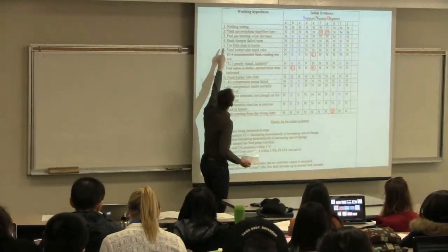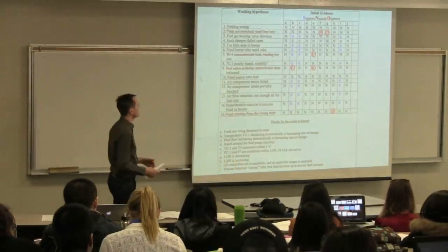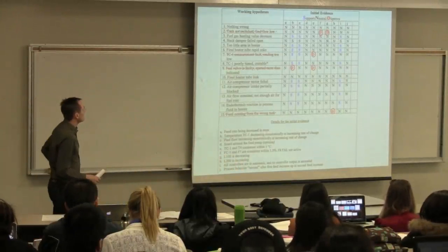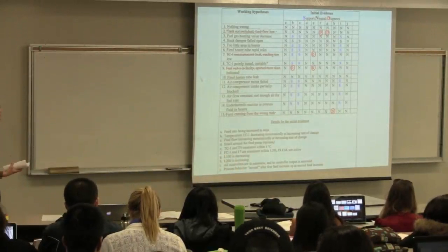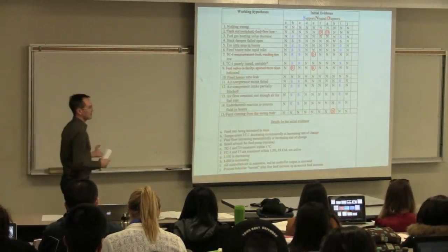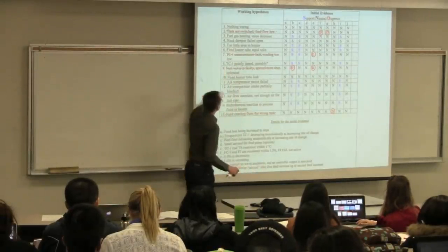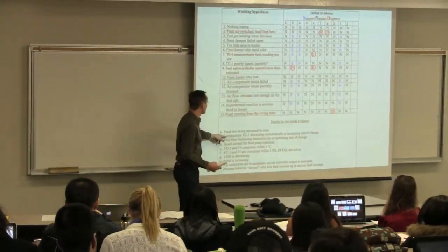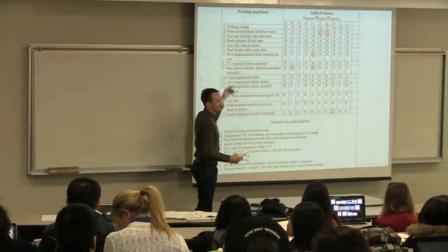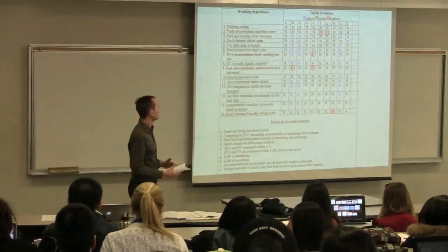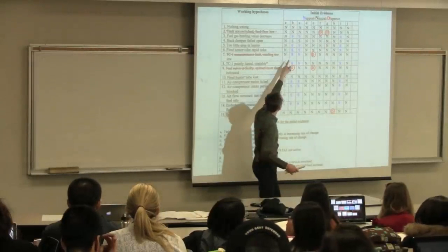Let's take a look then at, I'll look at the third one first, one that does support. The fuel gas heating value has decreased. So if the fuel value has decreased, the energy content's decreased, the fact that TC1 is dropping off supports that assumption, right? The fact that the temperature that I'm recording is getting lower and lower supports the hypothesis that I've got less energy that I'm burning in the fuel. The stack damper being open can be supported by that as well, because if the stack damper is open, the temperature 1 there should be decreasing. The too little area in the heat exchanger, if somehow the area in the heat exchanger has dropped off, that's going to show up as the temperature TC1 decreasing. So I can write an S there in that column.